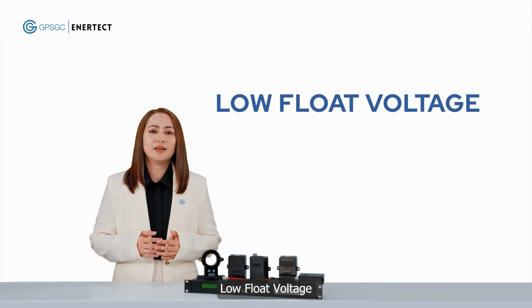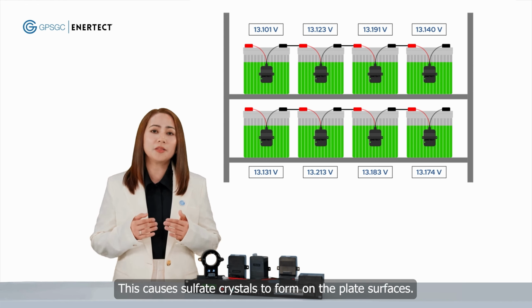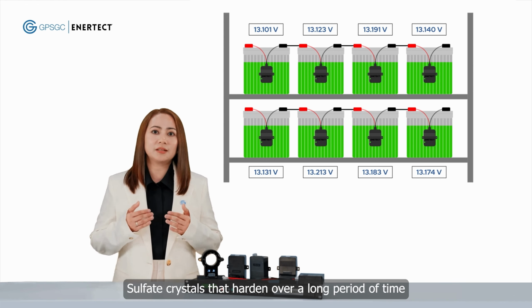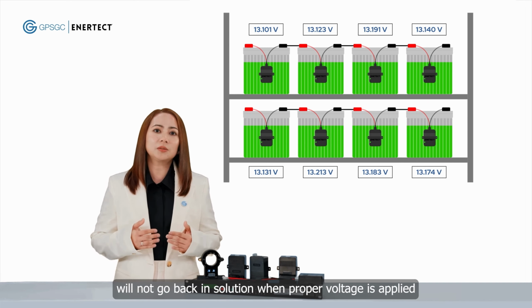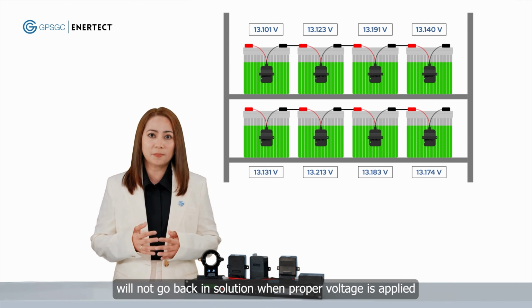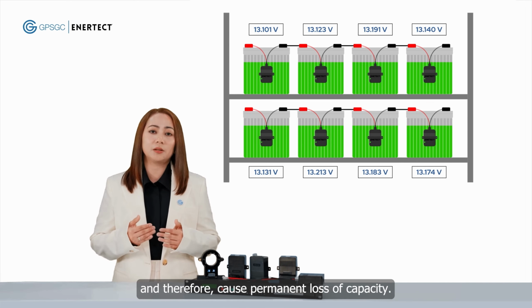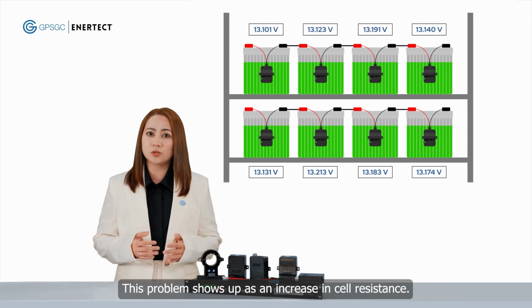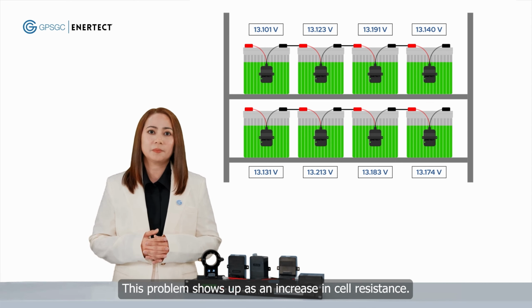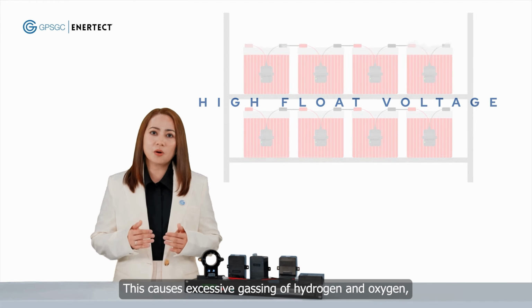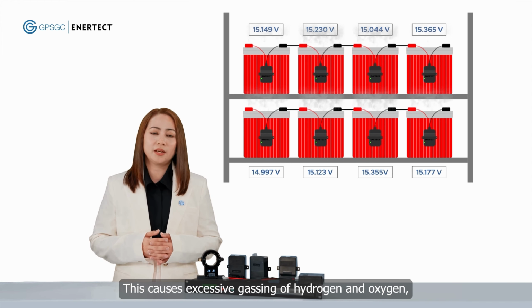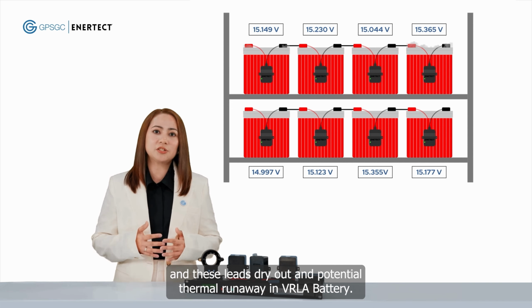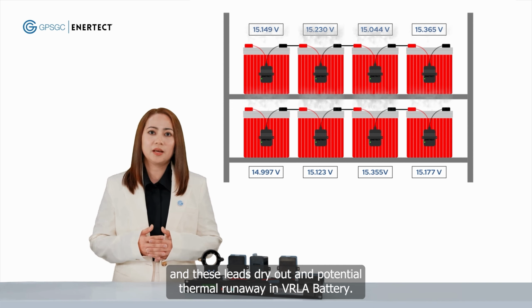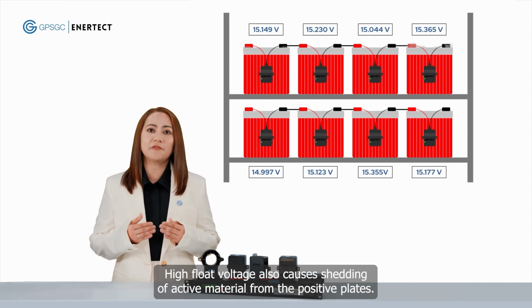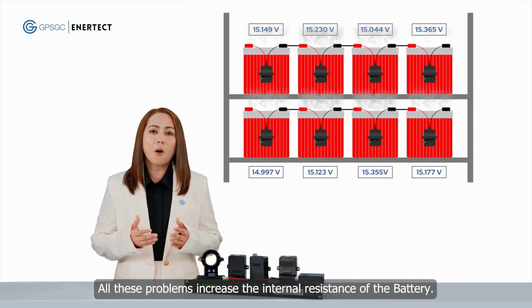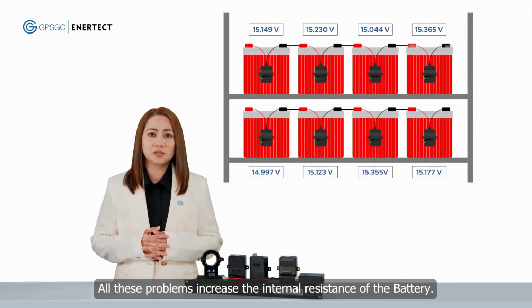Low float voltage. This causes sulfate crystals to form on the plate surfaces. Sulfate crystals that harden over a long period of time will not go back in solution when proper voltage is applied and therefore cause permanent loss of capacity. This problem shows up as an increase in cell resistance. High float voltage. This causes excessive gassing of hydrogen and oxygen, and these lead to dry out and potential thermal runaway in VRLA battery. High float voltage also causes shedding of active material from the positive plates. All these problems increase the internal resistance of the battery.